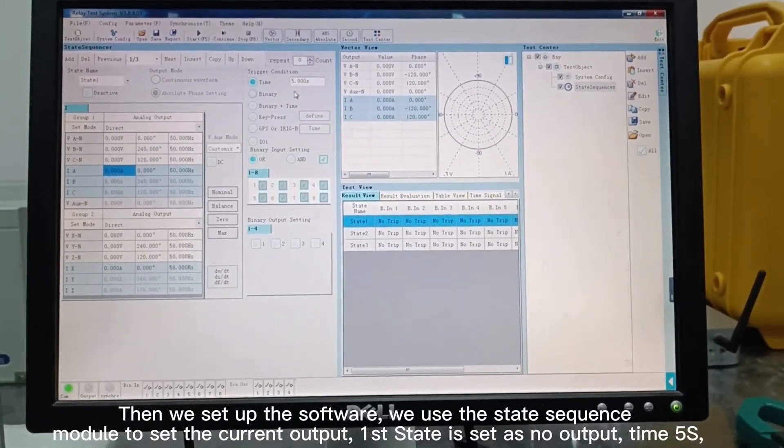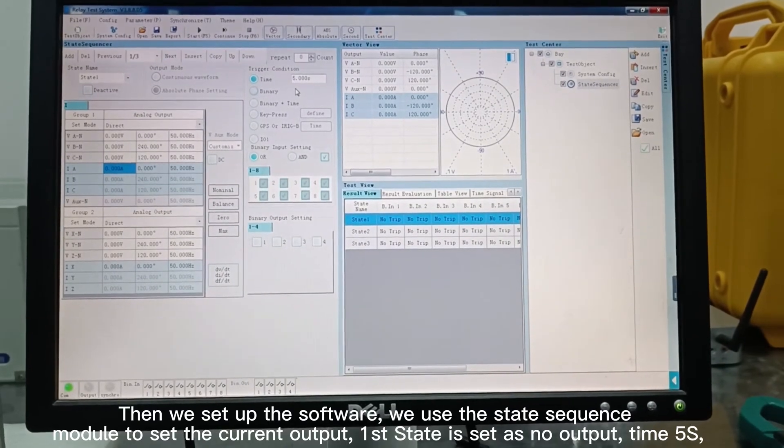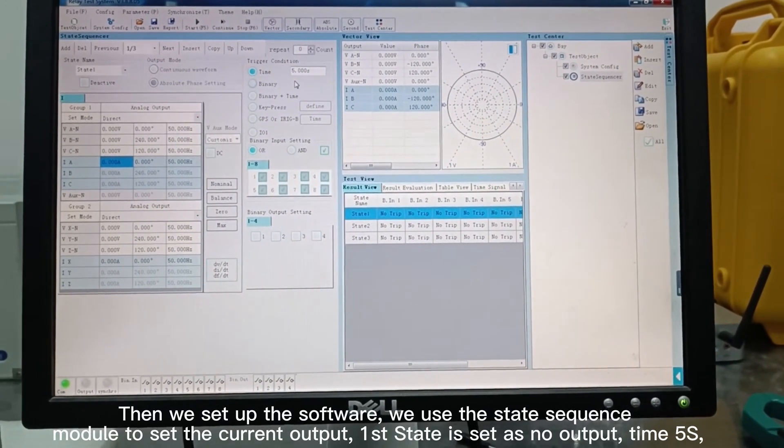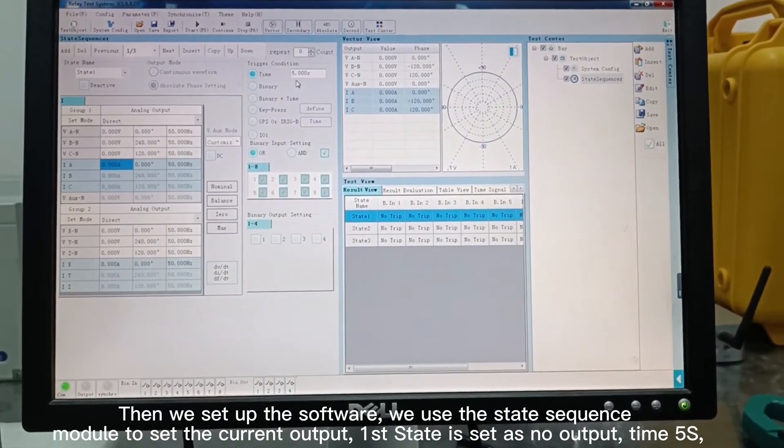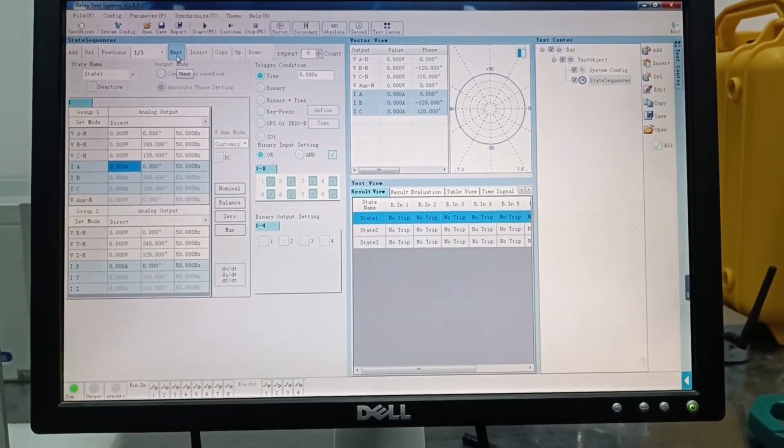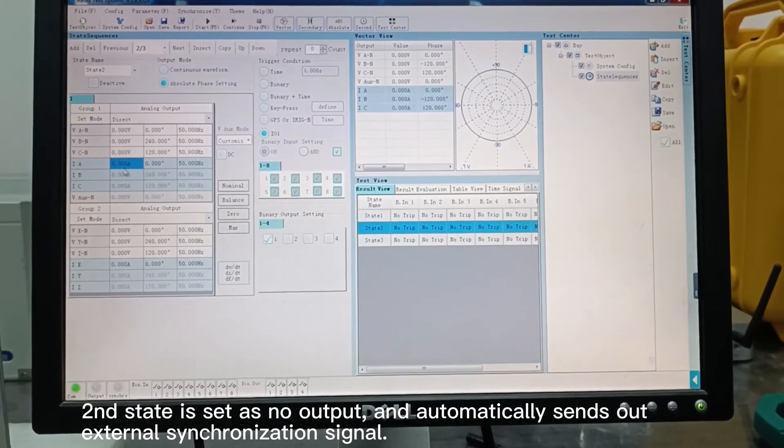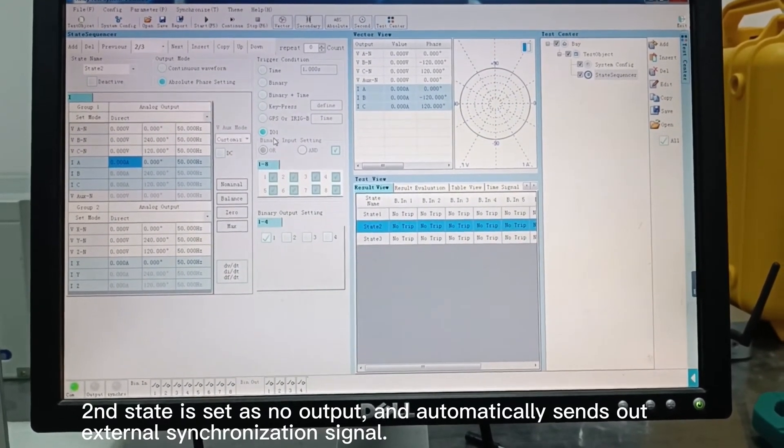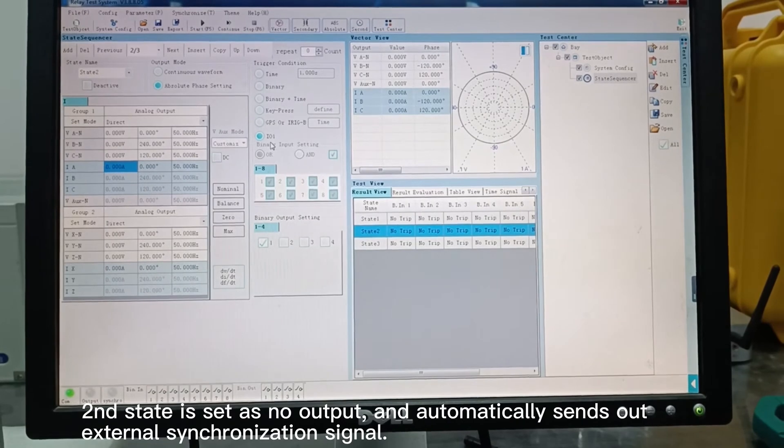To set up the software, we use the state sequence module to set the current output. First state is set as no output, time 5 seconds. Second state is set as no output and automatically sends out external synchronization signals.